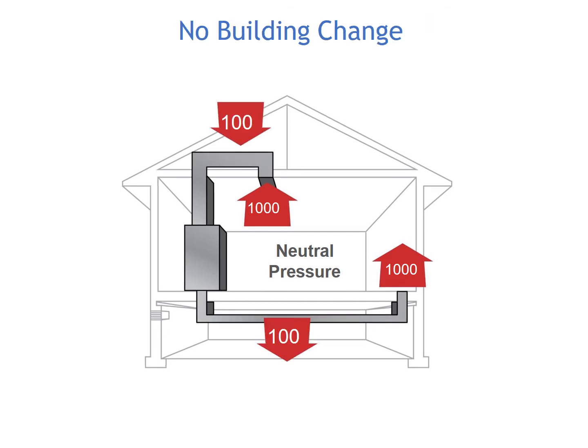The last slide that we looked at showed that the system was completely balanced. You had 1,000 CFM going into the unit, and you have 1,000 CFM coming out of the supply side of the unit. The other option is that you may be pulling additional air from the return side of the system, then you also have 1,000 coming out of the supply, but you may be losing a little bit to leakage. If you're losing the same amount as you're sucking in on the return, this system can still be neutral pressure, meaning you don't have any negative air going on in this situation.